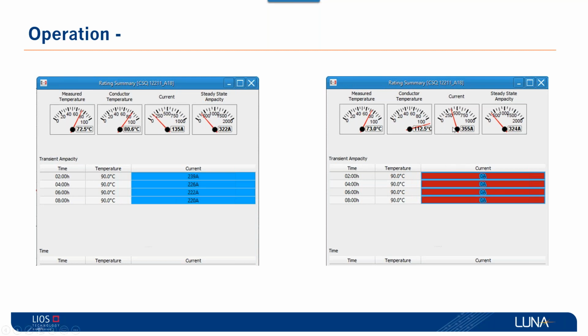And if they keep going higher and higher, this is the information that they're getting from the dashboard to tell them that they cannot push any more ampacity. They already reached 112 degrees Celsius at the conductor. So now this changes the operation quite a lot. If you have secondary or primary circuits where you have a dedicated line, let's say a data center or a manufacturing plant, and those guys have peak hours where they need to produce more over time, you can tell them that I'm giving you 239 amp or 1000 amp for 1 hour, 2 hours without damaging my line.